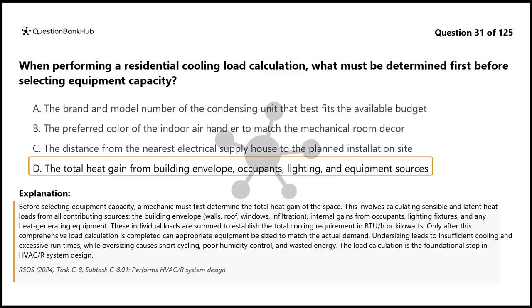These individual loads are summed to establish the total cooling requirement in BTU/h or kilowatts. Only after this comprehensive load calculation is completed can appropriate equipment be sized to match the actual demand. Undersizing leads to insufficient cooling and excessive run times, while oversizing causes short cycling, poor humidity control, and wasted energy. The load calculation is the foundational step in HVAC/R system design.